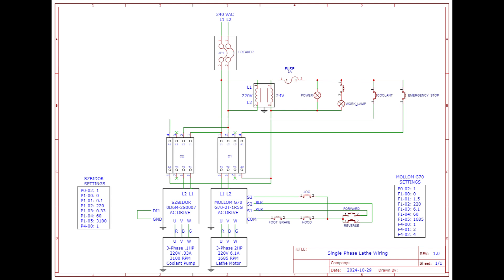It next feeds the work lamp, which has a switch, and then it feeds the coolant switch on the front panel. That coolant switch feeds terminal A1 of the C2 contactor. Whenever that coolant switch is on, A1, A2 energized, that turns on the contactor. The L1 and L2 220 volt goes through the contactor and powers on the AC drive or VFD, which in turn powers the three-phase coolant motor.